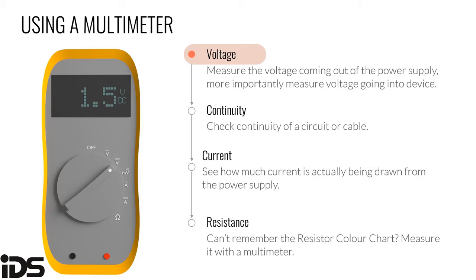Always measure voltage at the device, not just at the panel or power source. For example, you might measure 12.3 volts at the panel, but with a 50-meter run with high resistance, you could only be getting 11 volts at the keypad or detector. Cable has its own resistance per meter, and the further you run, the lower the voltage will be. Very important — always measure at the device, or you could spend a whole day troubleshooting and not realize the problem is simply insufficient voltage at the device.